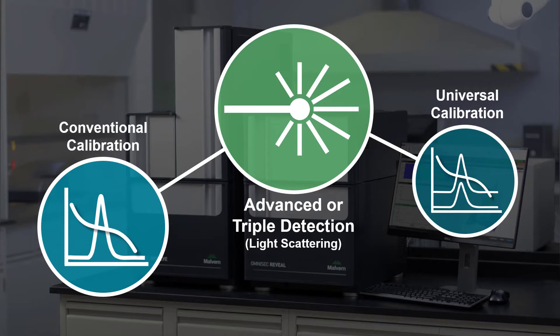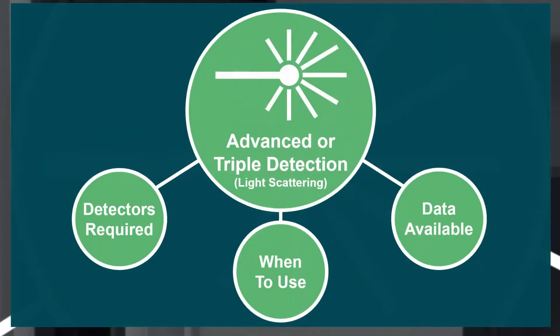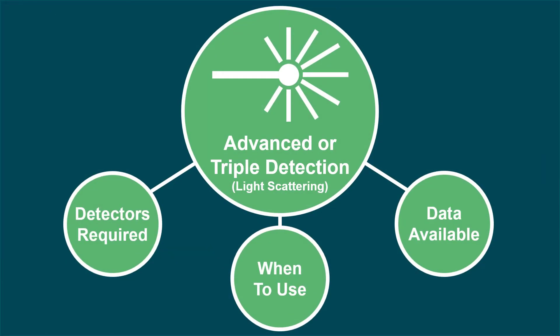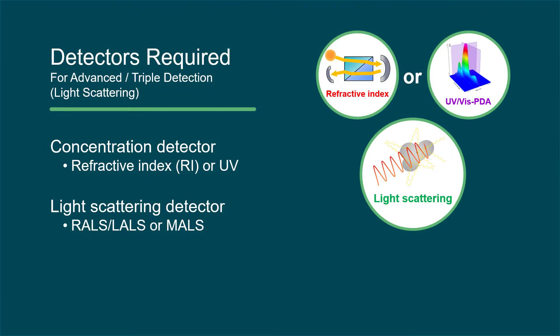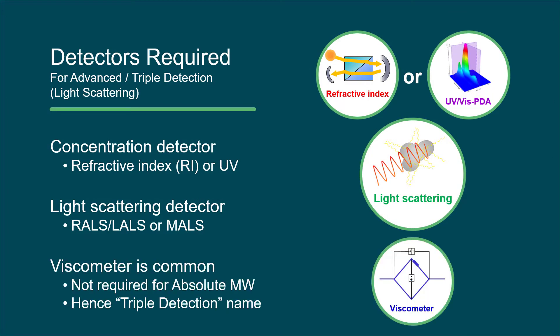We'll start with advanced or triple detection. As mentioned earlier, this method refers to molecular weight calculation with a light scattering detector. Therefore, the minimum configuration includes both a concentration and a light scattering detector. A viscometer detector is commonly added, hence the name triple detection, but is not required for absolute molecular weight determination.